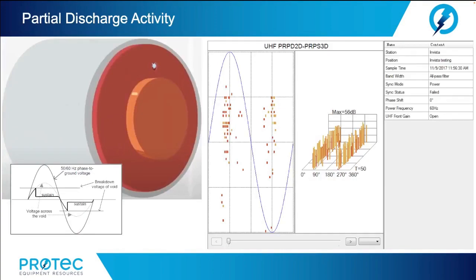Now, we know that partial discharge signals are produced as the sine wave reaches a positive or negative peak, or trough, or peak voltage stress. The sine wave peaks and troughs are exactly 180 degrees apart, 16.66 milliseconds divided by 2, or every 8.3 milliseconds. The partial discharge pulses continue to arrive with intervals equal to 8.3 milliseconds or multiples of 8.3 milliseconds, 180 degrees apart, with some fluctuation due to partial discharge inception and extinguish points.